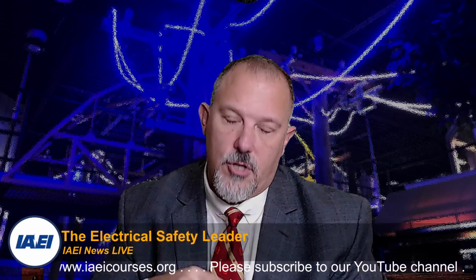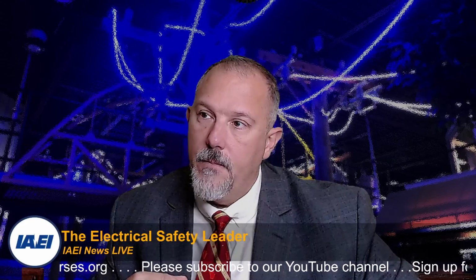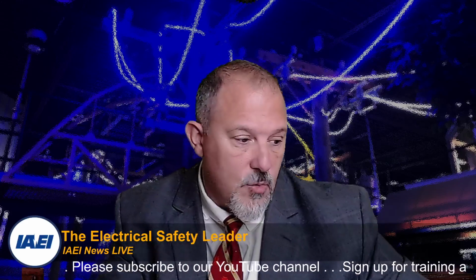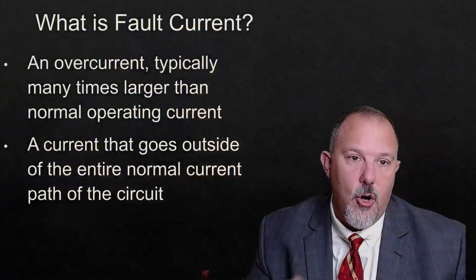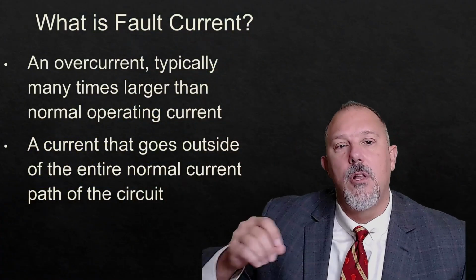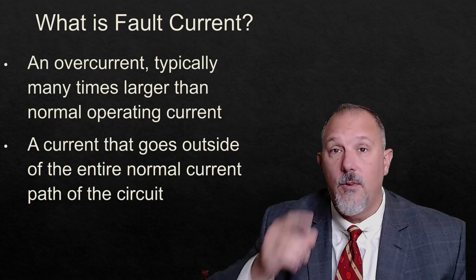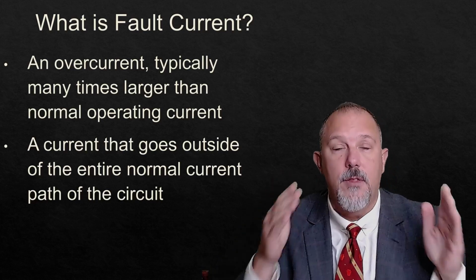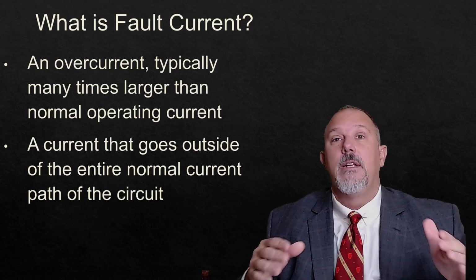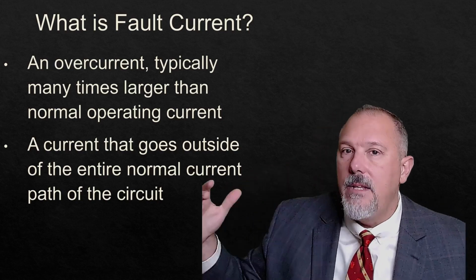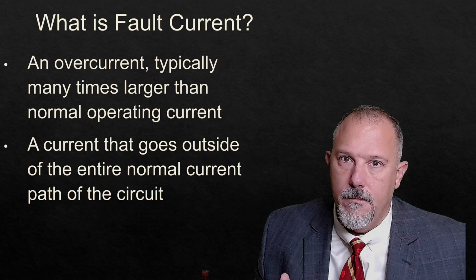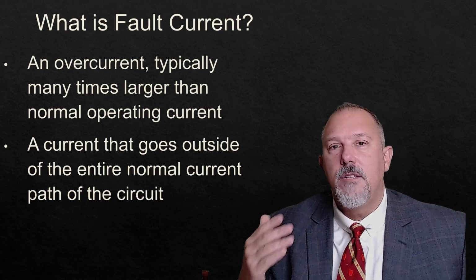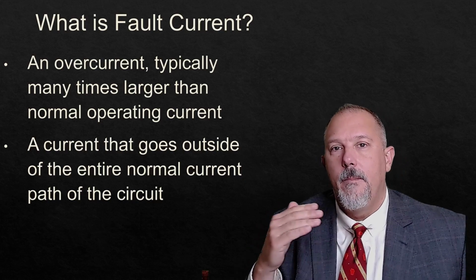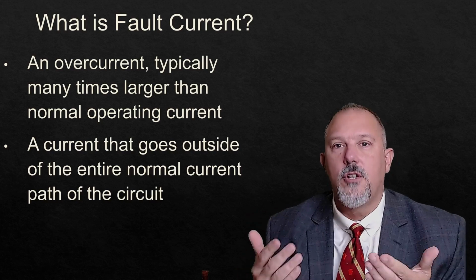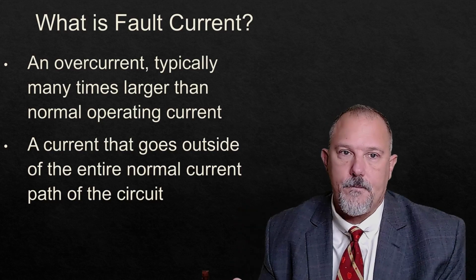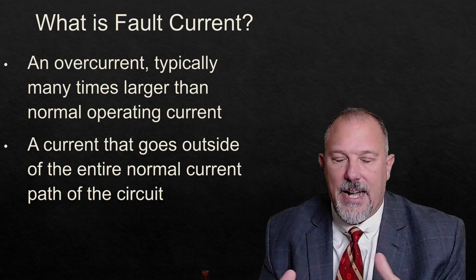So a fault current is an overcurrent, because it is in the definition. It's an overcurrent many times larger than normal operating current. Why? Because I have reduced the length of the circuit. I have taken impedance out. I've taken the impedance of the load out. And because my impedance is much lower, my short circuit current will go much higher. It's outside of the path.